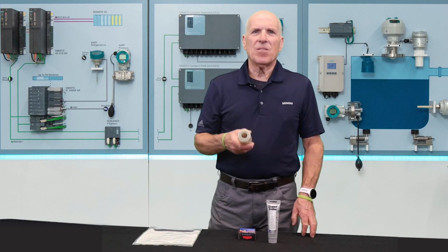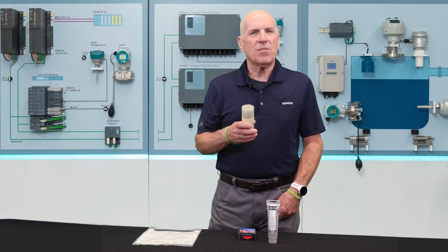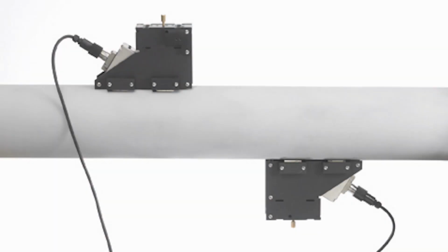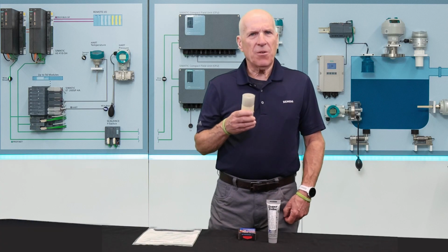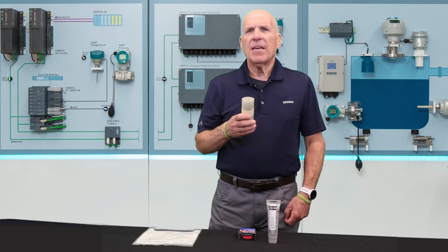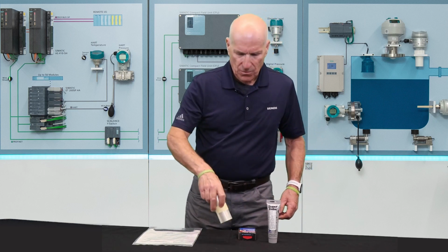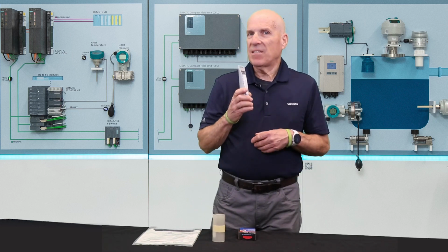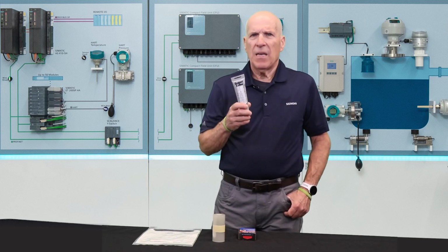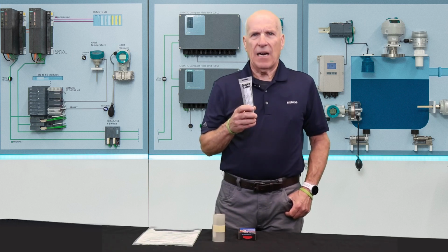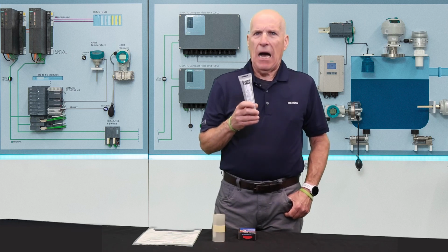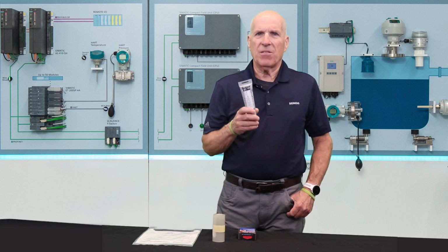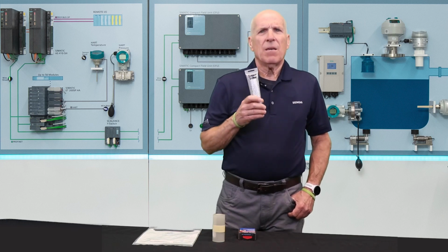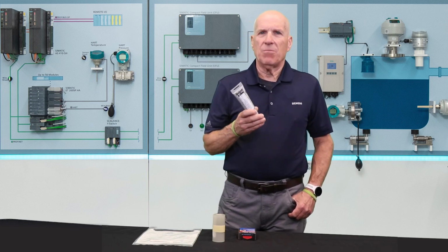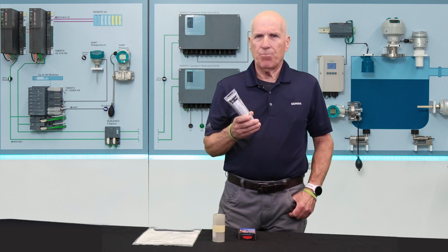The mounting guide is a tool that's necessary if you'll be installing your sensors in direct mode, where they are on opposite sides of the pipe from each other. The use of this tool and the procedure for mounting flow sensors in direct mount is covered in separate videos. Coupling compound is a necessity for all clamp-on flow meters. It's applied to the face of the sensor that contacts the pipe, creating an optimal path for the sonic energy to transfer into the pipe wall. Its function is similar to what medical teams use when they perform a sonogram.